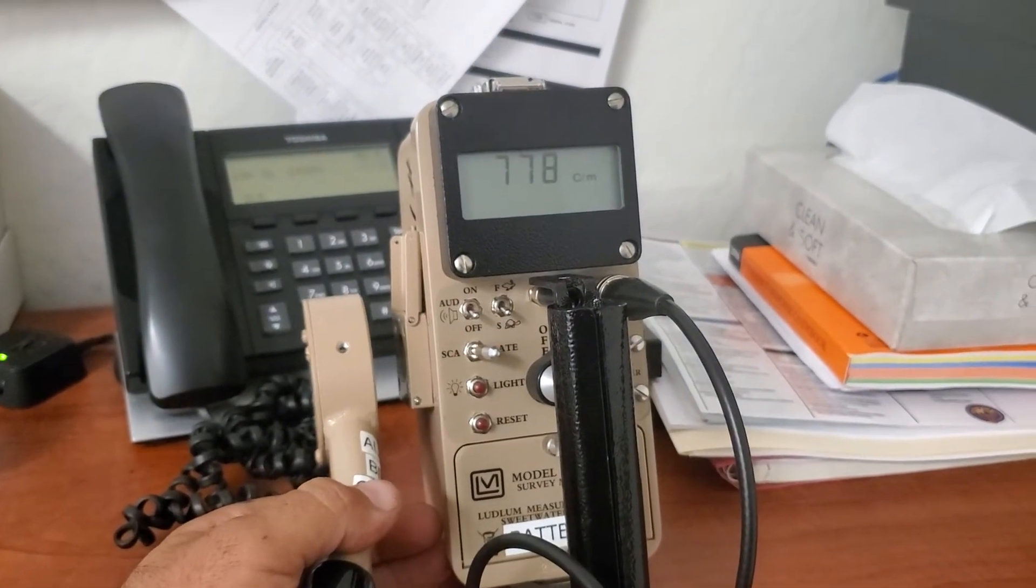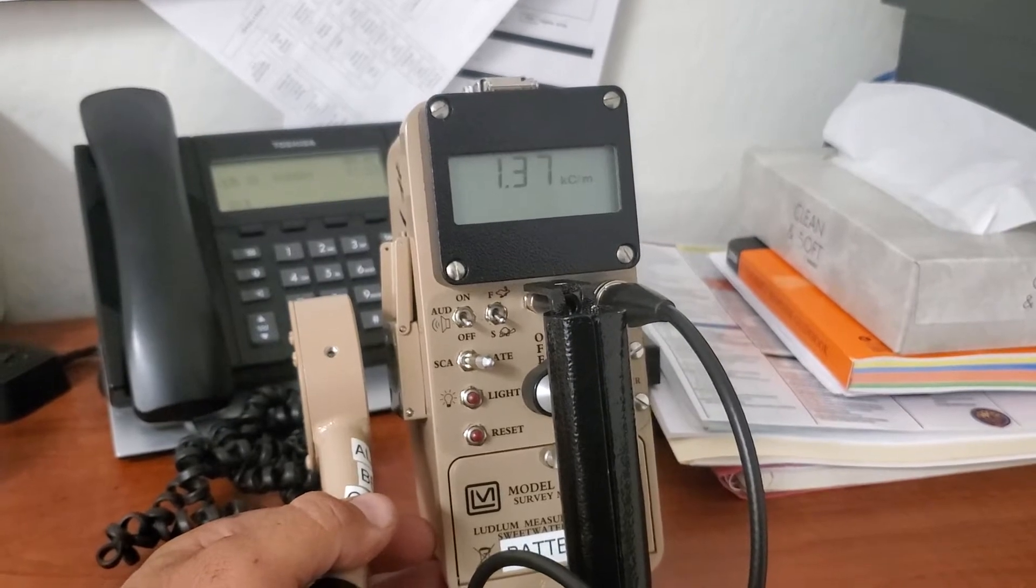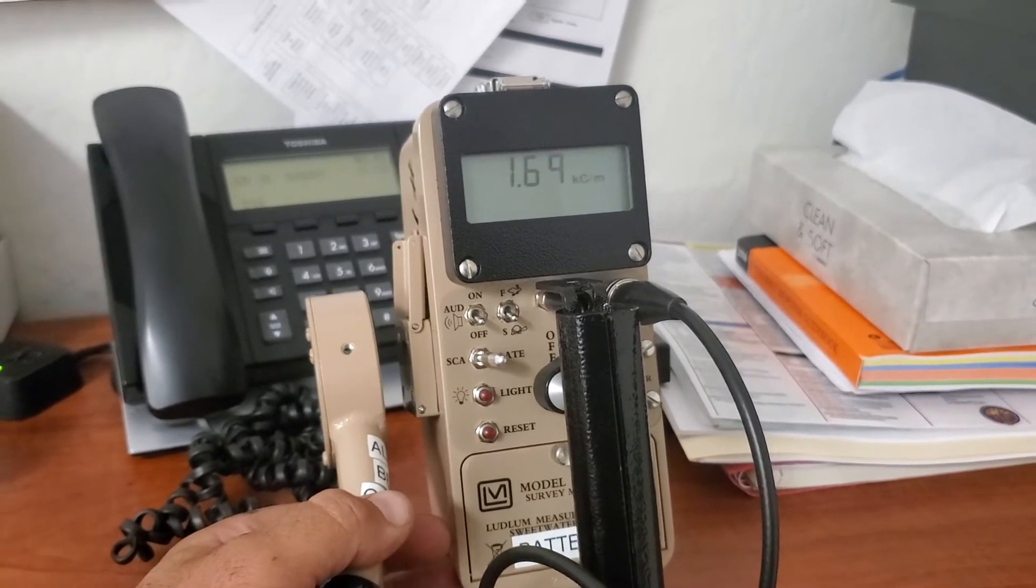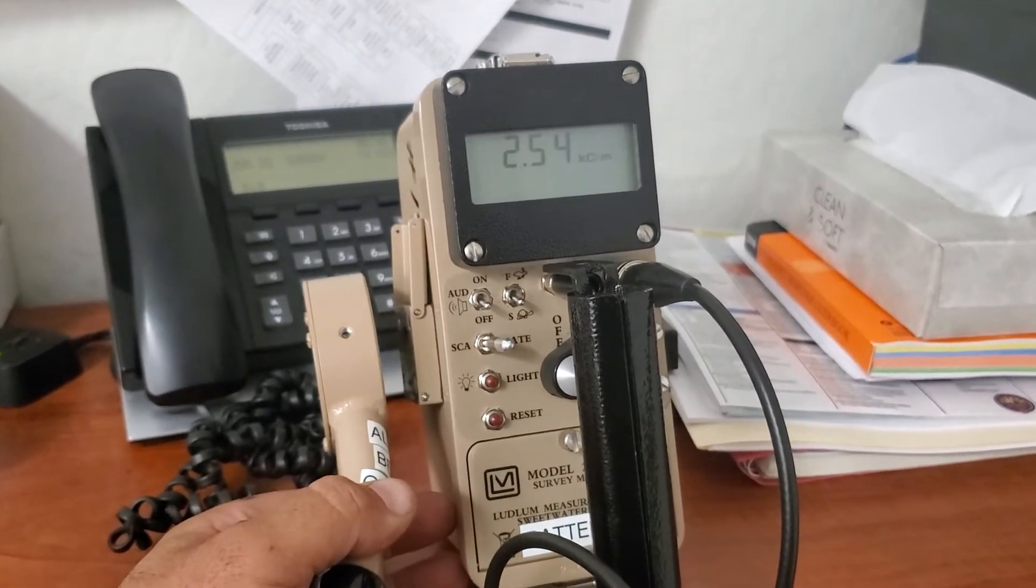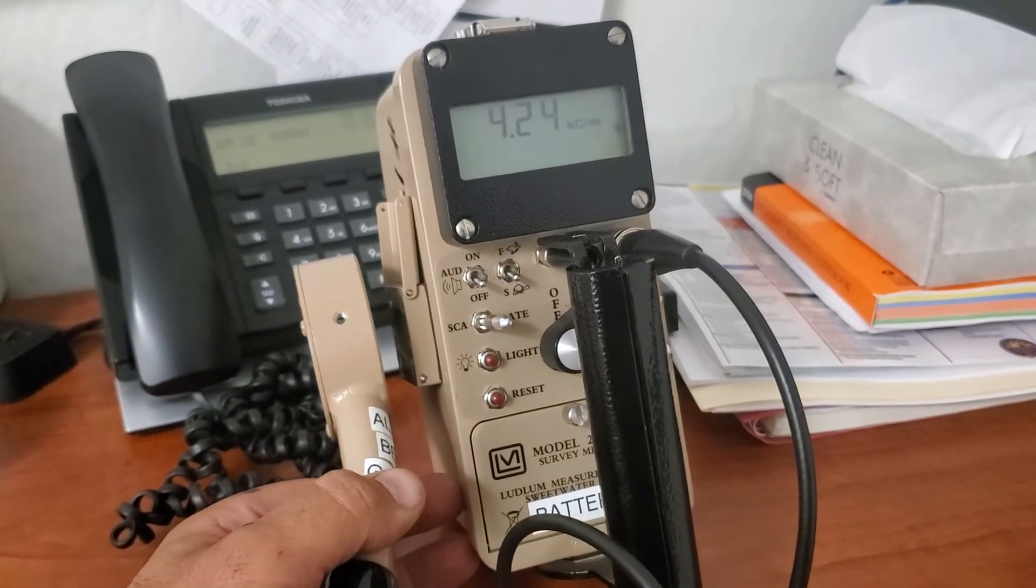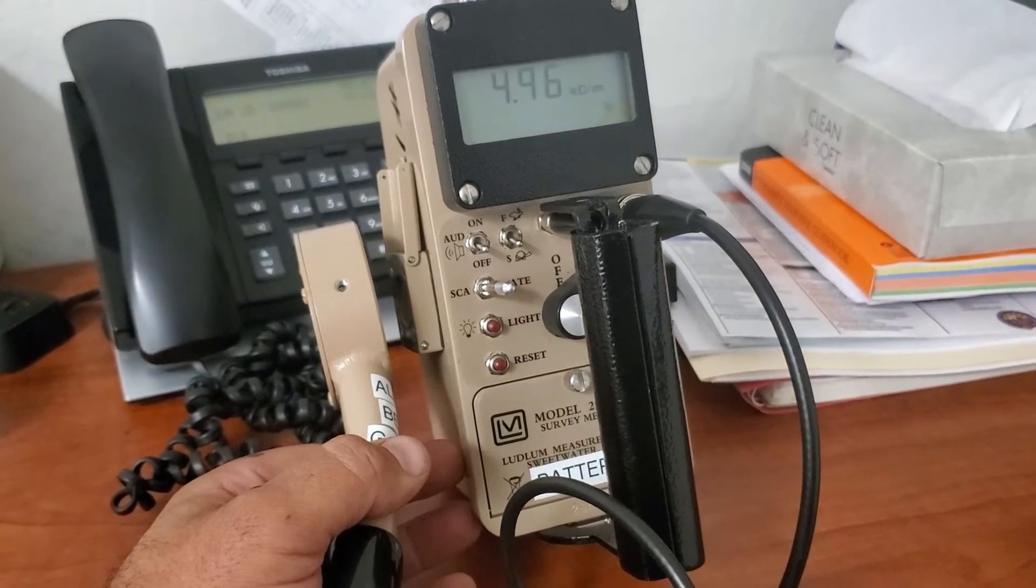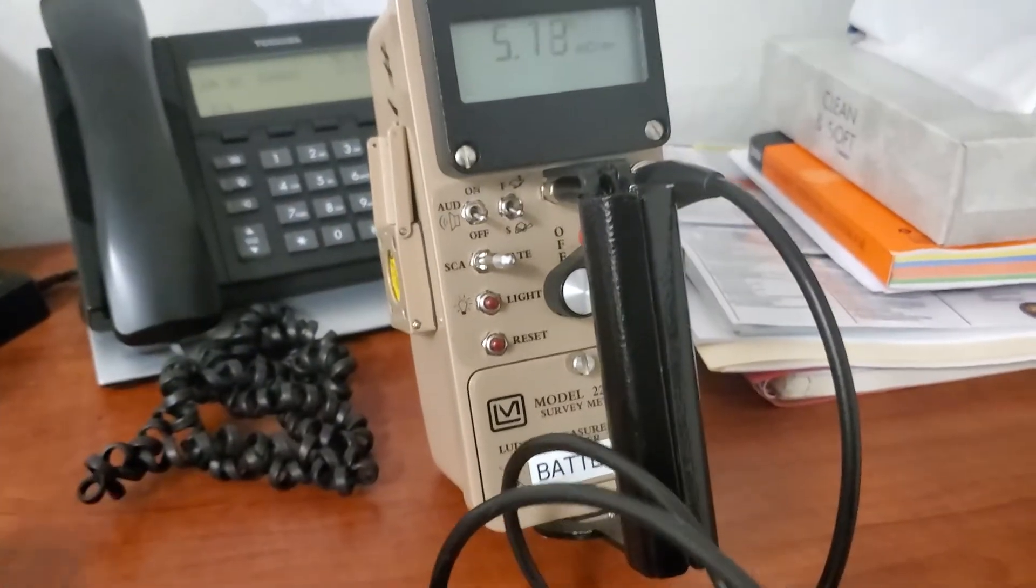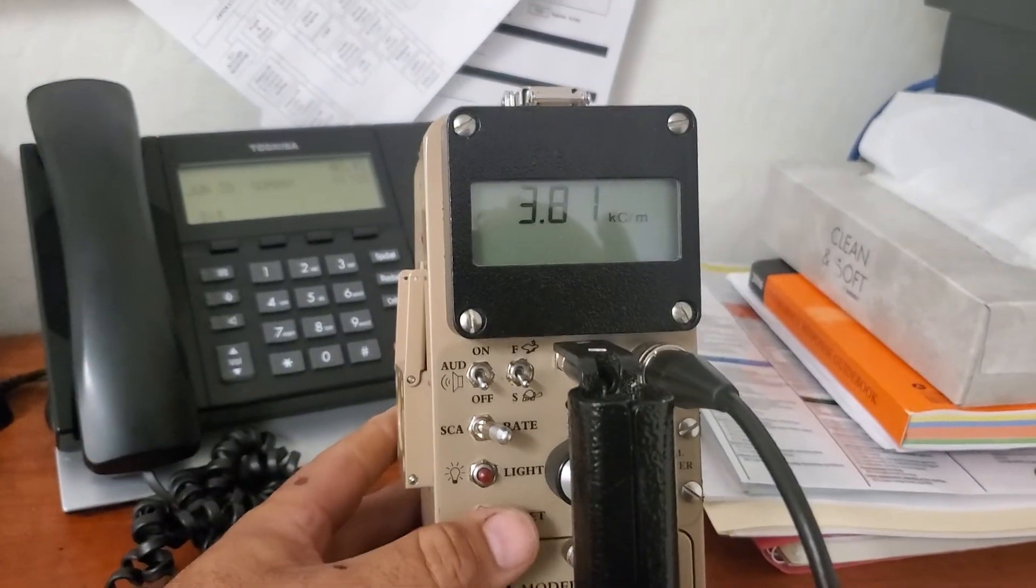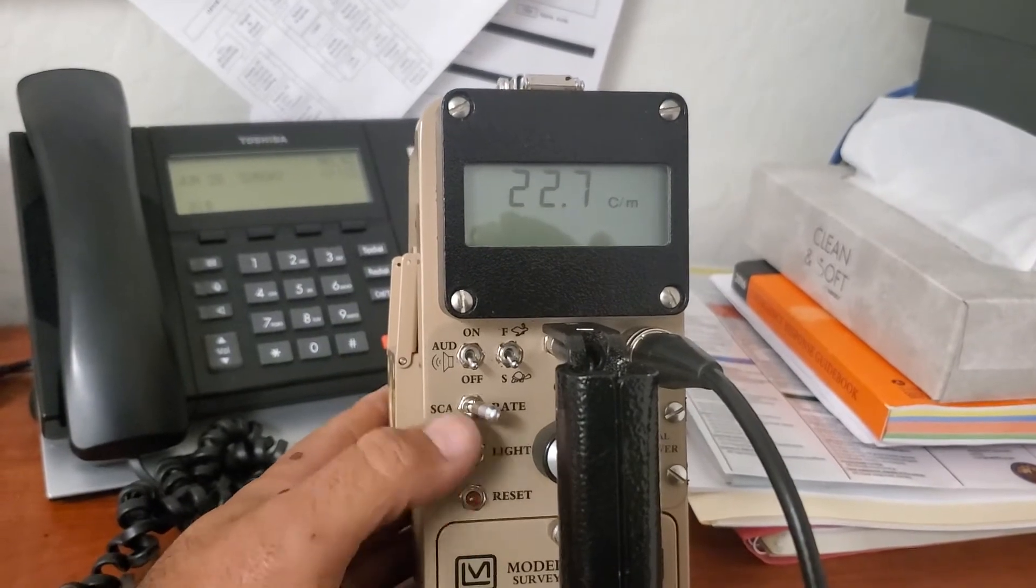We'll put this here. See how it auto ranged there, gave you that decimal point. That's a cool feature. We don't have to deal with it. So it keeps creeping up. And if we left it here, I'm sure we'd probably get to the end range, but for sake of time, we're just going to keep moving on. So you get it real saturated. See how it takes a while to come back down? You don't want to wait for it. Hit this reset button and it zeroes it right back out.